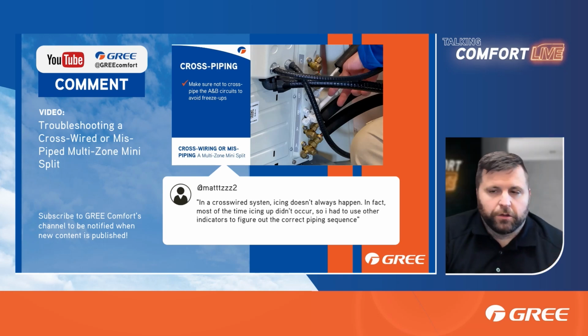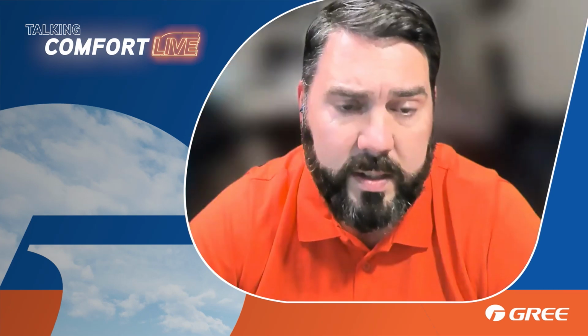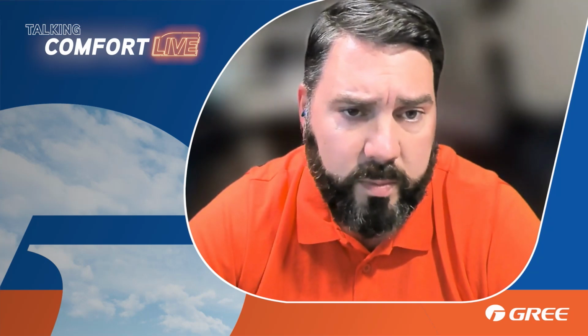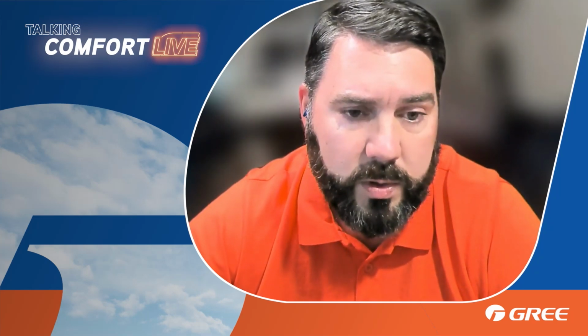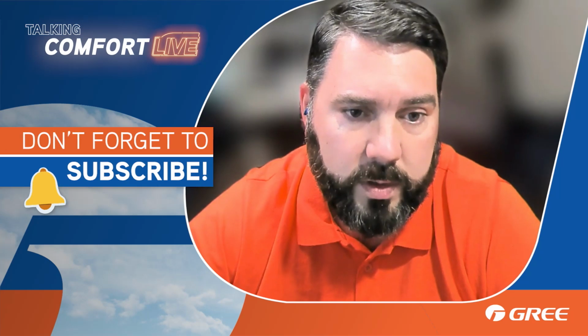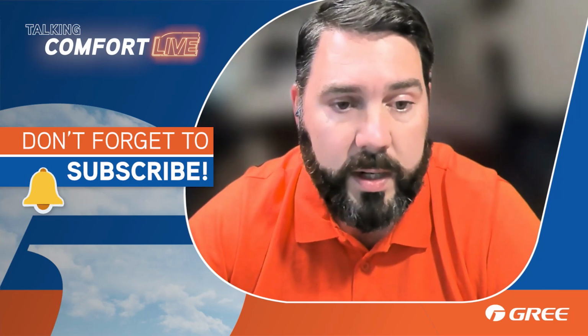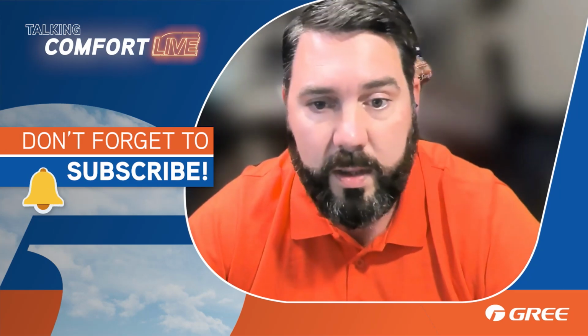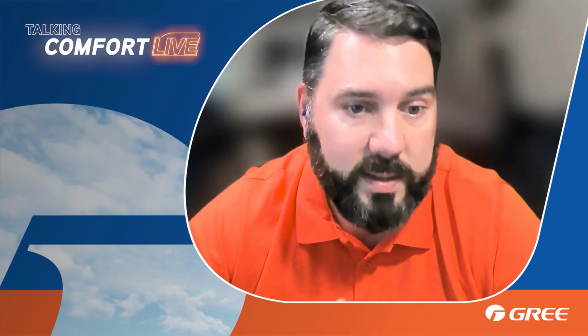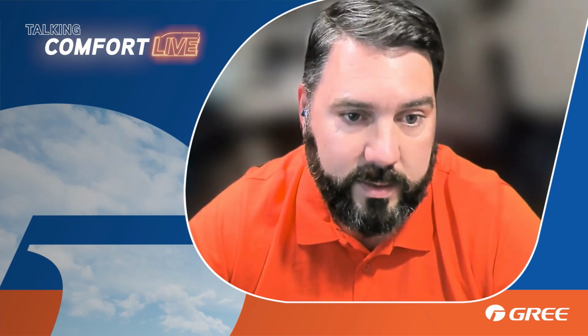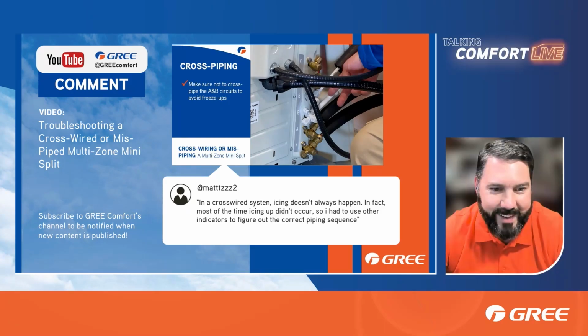So the point's not necessarily that ice occurs, I guess it's just which one's calling, which one's cooling, and it's not supposed to be cooling. These systems will try to adjust themselves the best they can because it knows what temperature the coil is through the coil temperature sensor. So it's going to try to adjust itself - the EEV, the compressor speed - to try to avoid icing. It knows that icing's not great for operation.